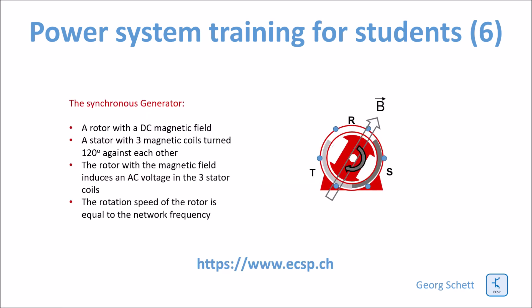Most generators connected to the grid are synchronous generators. Synchronous generators consist of a rotor with a DC magnetic field. Then we have a stator with three magnetic coils, which are turned 120 degrees against each other. The rotor with its magnetic field induces an AC voltage in the three stator coils, and the rotation speed of the rotor is equal to the network frequency. That's why it's called a synchronous generator.